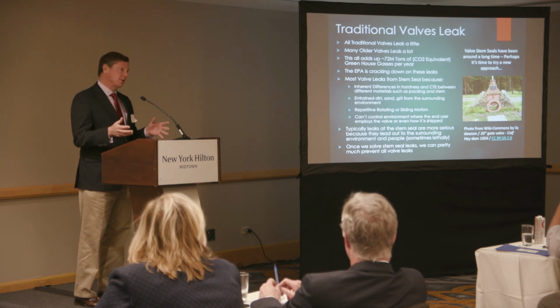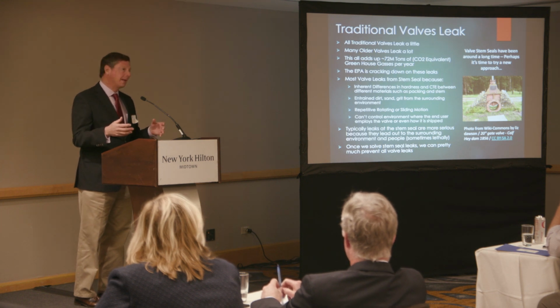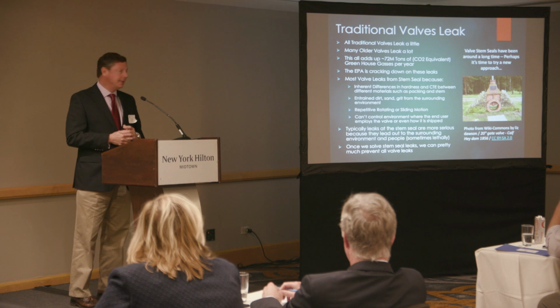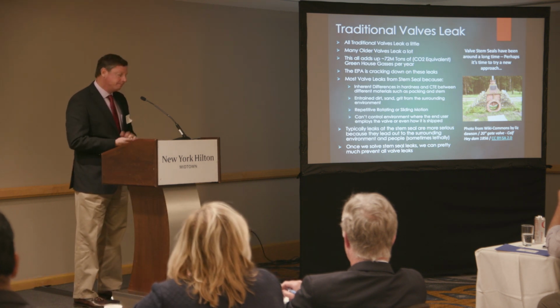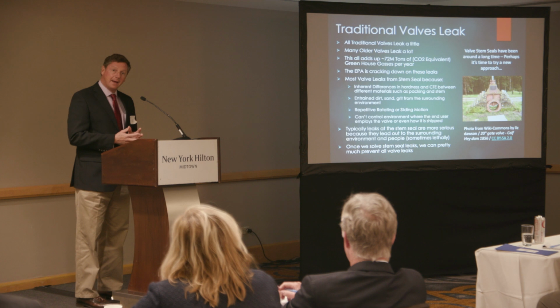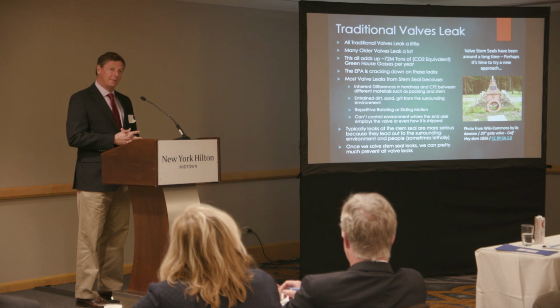If it goes across the ocean in an ISO container on the side, that perfectly circular high-tech packing ends up as an ellipse when it arrives. So a brand new valve being installed in a refinery in the Mideast may have a leaking packing right away. And if it doesn't, it starts to leak some over time. These leaks add up. It's about the equivalent of 72 million tons of CO2 in terms of greenhouse gas emissions.